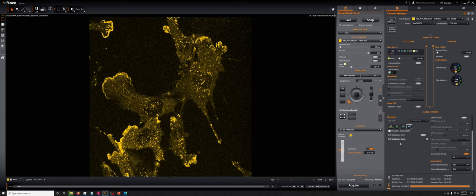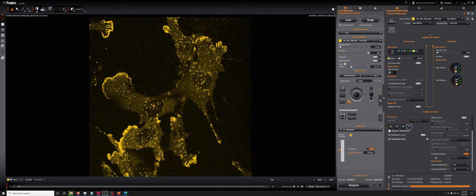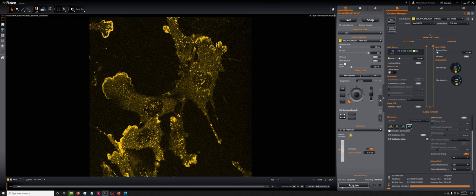Another thing you can do to improve the speed is increase the binning. So what binning does is it combines pixels, so it reduces your resolution. It increases your signal to noise, and it can also increase the speed.